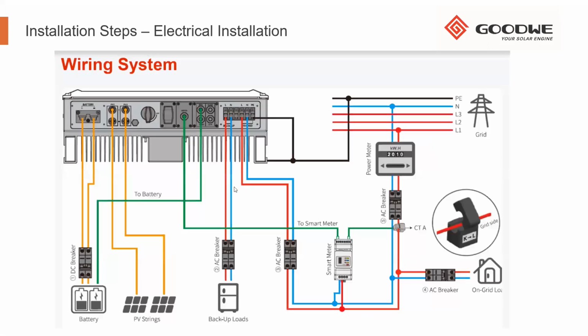Here's just a brief overview of the installation for the ES inverter. So you'll see we've got the on-grid input, which is the bidirectional grid input. Then we've got the backup output. Depending on your grid type, you'll see this is an unmarked terminal. In South Africa, we'll generally connect this terminal up to the backup, to the earth terminal as well. That will just ensure that we don't have a floating neutral should the grid fail.